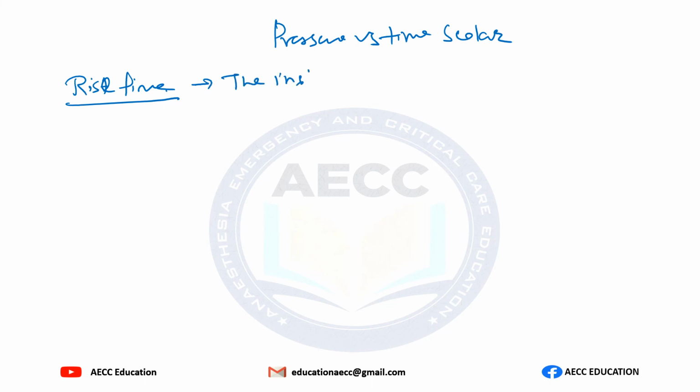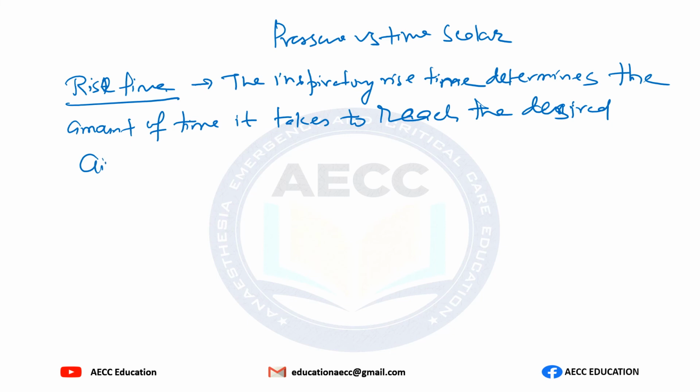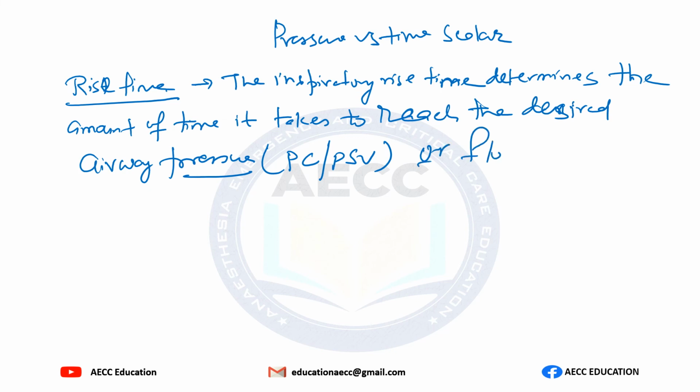The inspiratory rise time determines the amount of time it takes to reach the desired airway pressure if the patient is on pressure control or pressure support ventilation, or flow rate if the patient is on volume control ventilation.